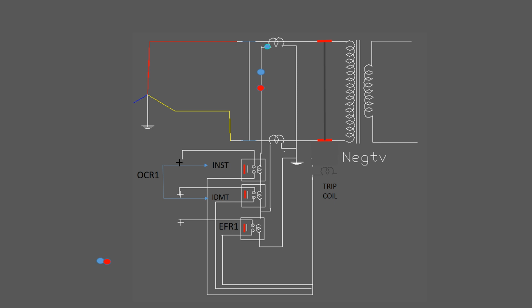First, see, we have OCR1 relay with two elements, instantaneous and IDMT. In instantaneous, you have seen it is set to 25% more than the LV fault maximum current. That means during any LV fault, the instantaneous OCR1 will not trip. It will trip only for a fault on the 132 kV side with higher current.